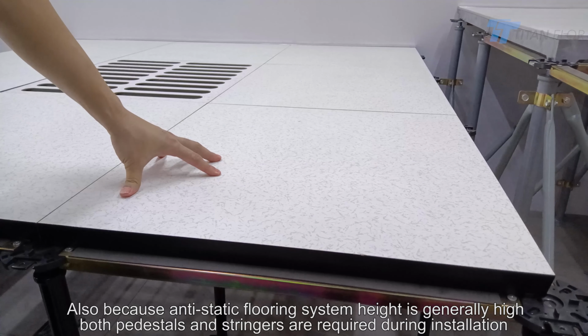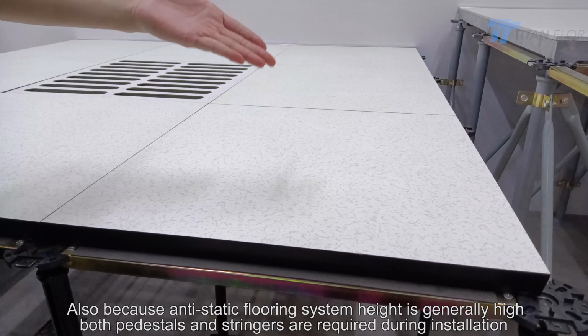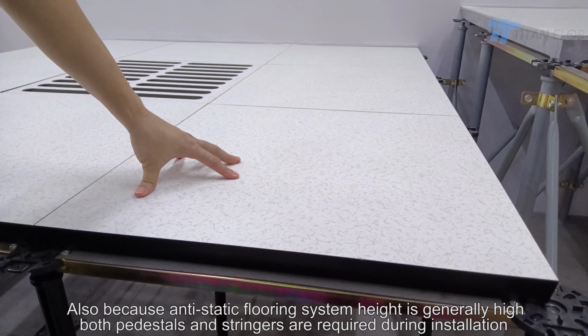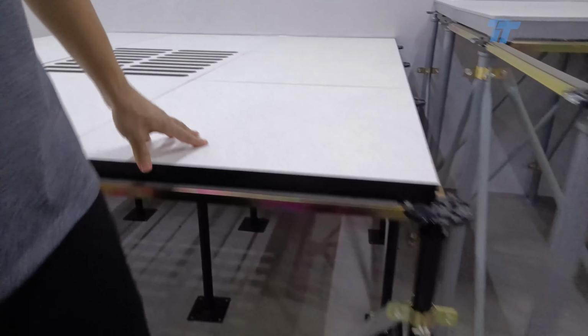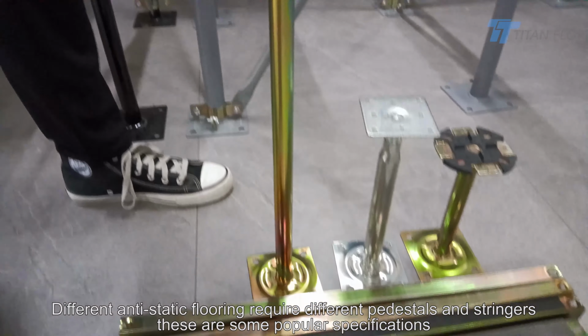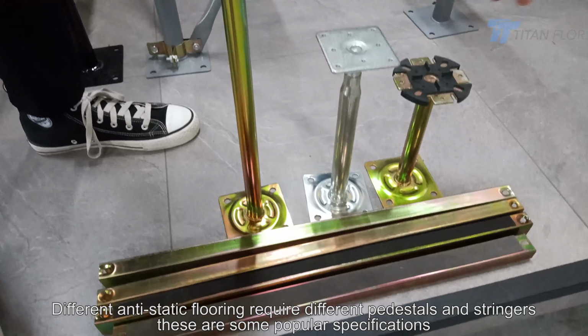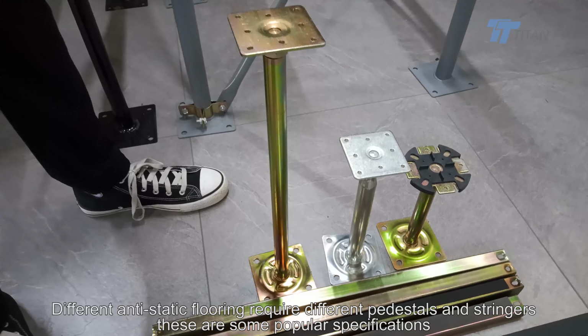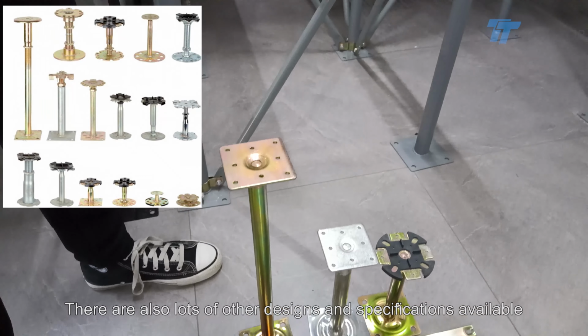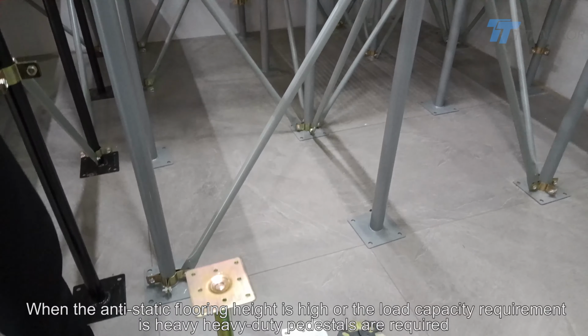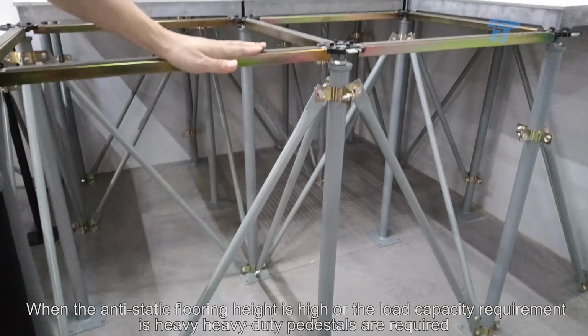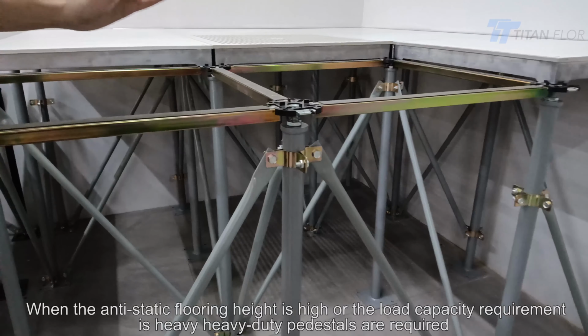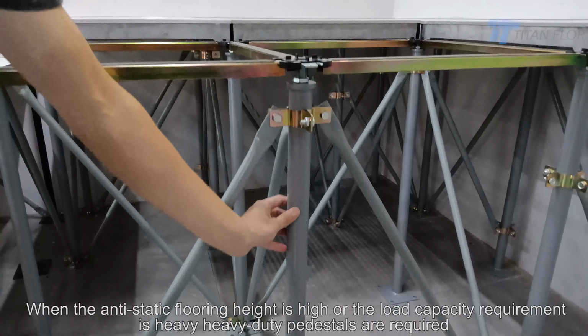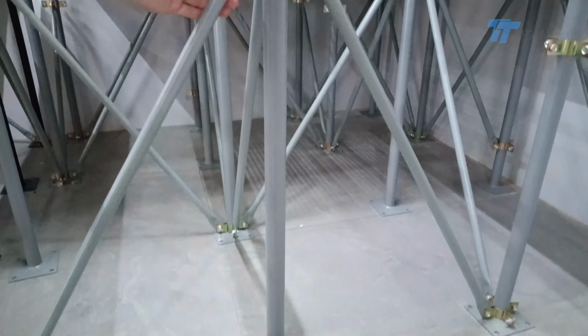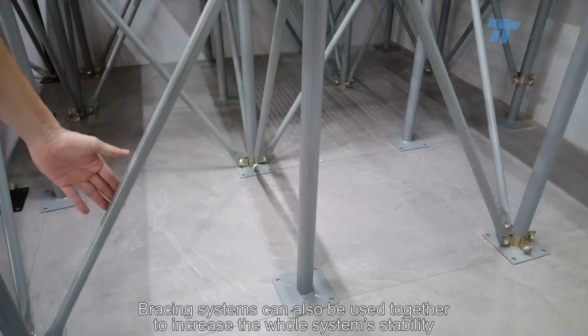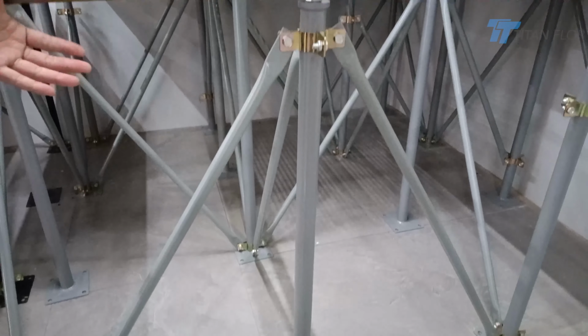Also, because anti-static flooring system height is generally high, both pedestals and stringers are required during installation. Different anti-static flooring require different pedestals and stringers. These are some popular specifications. There are also lots of other designs and specifications available. When the anti-static flooring height is high or the load capacity is heavy, heavy-duty pedestals are required. Bracing system can also be used together to increase the whole system's stability.